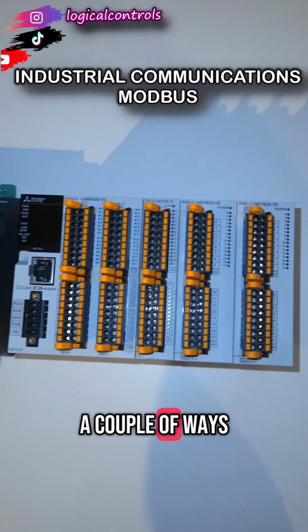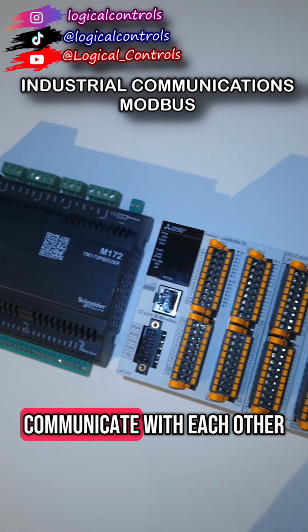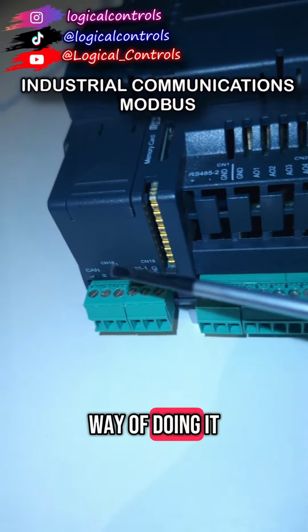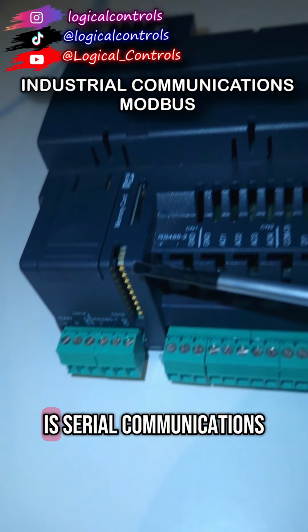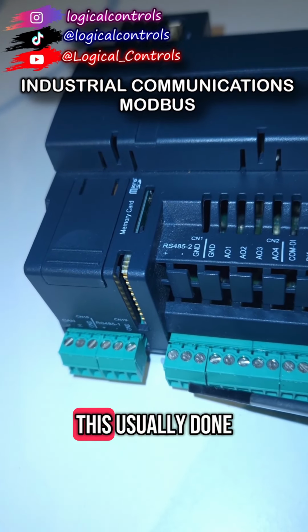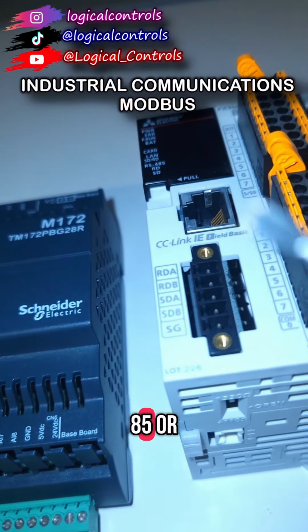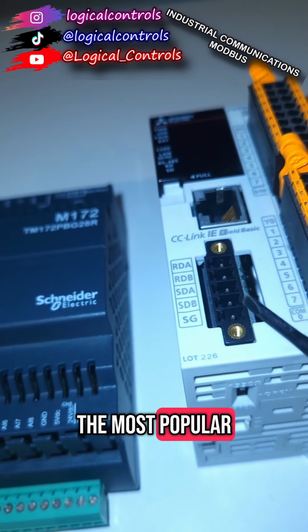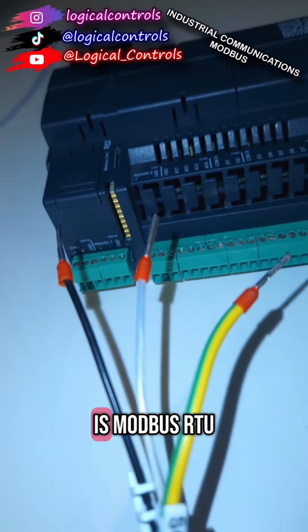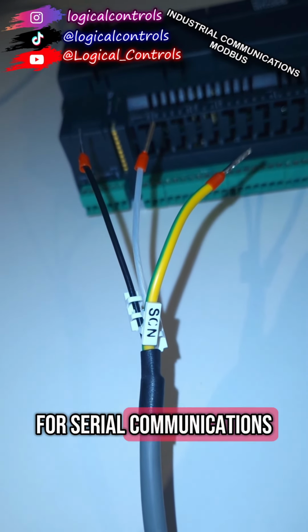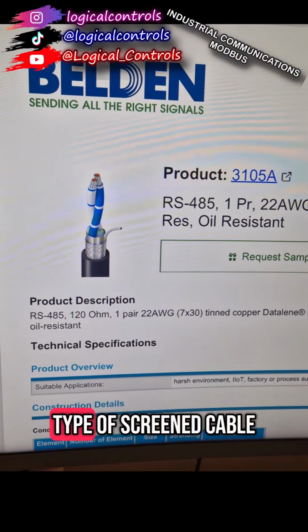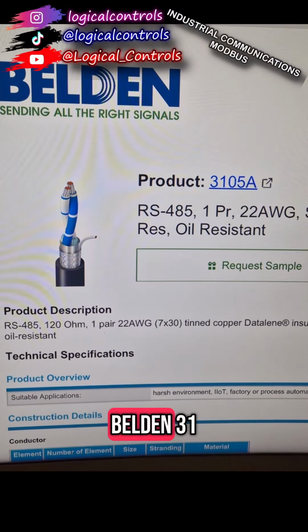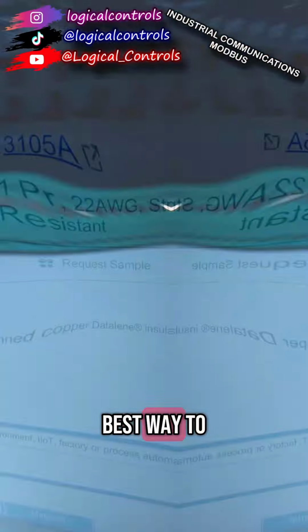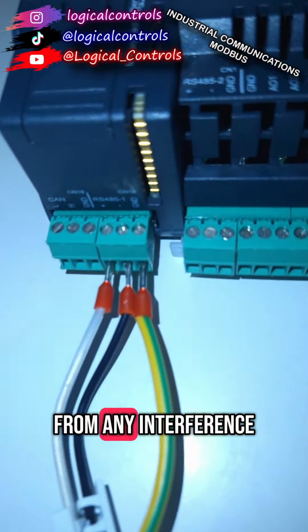Let's go over a couple of ways we can get different devices to communicate with each other. An old school way of doing it, but definitely still used in industry, is serial communications. This is usually done in the form of RS-485 or RS-232. The most popular protocol in industry that uses this is Modbus RTU. For serial communications, you need to use a particular type of screen cable, such as a Belden 3105A. This is the best way to make sure the data doesn't suffer from any interference.